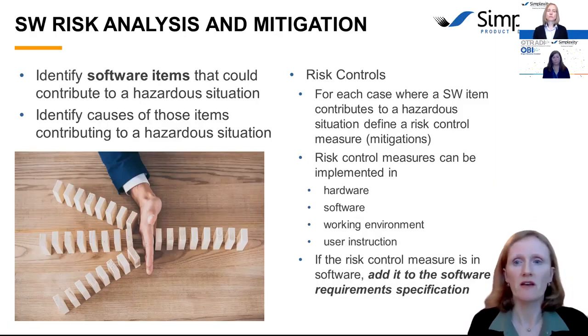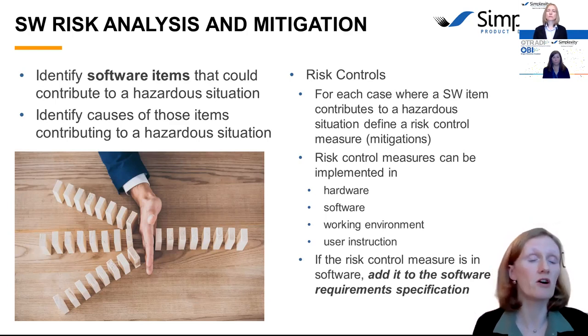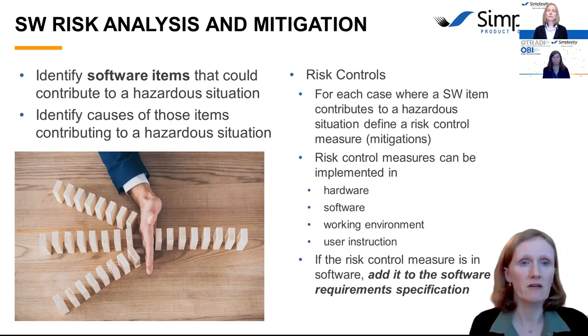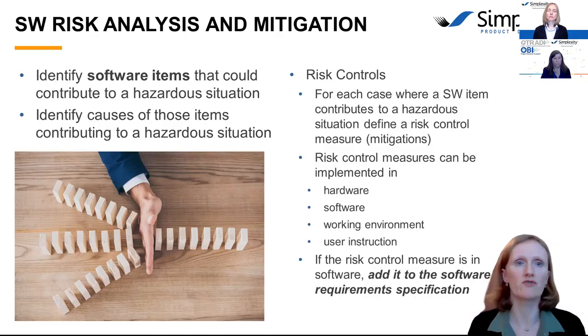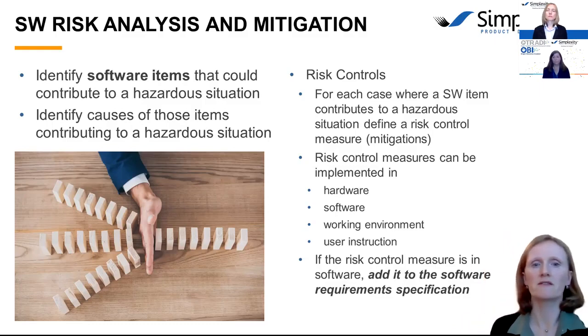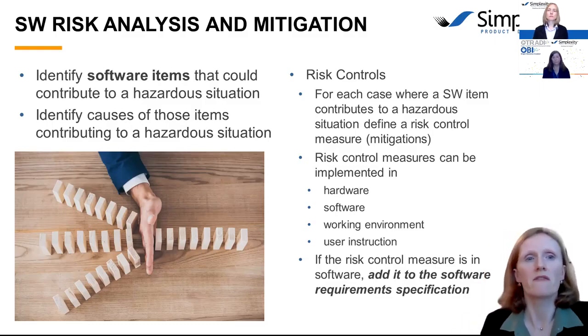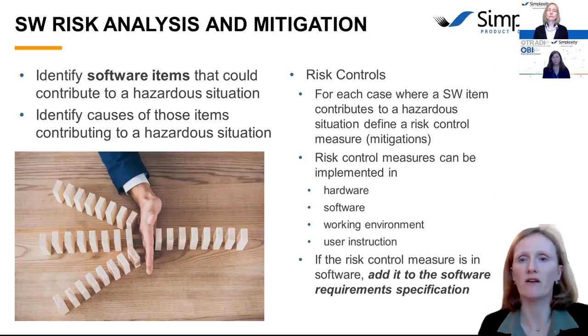Once we've identified those hazardous situations, if the risk is too high, as defined on that table, we would define a risk control measure. Those could be implemented in hardware, software, the working environment, or user instructions. And that's a priority order of where it is best to implement the risk control measure. It's obviously much safer to have a user prevented by the hardware from doing something that could lead to harm, as opposed to an instruction that warns them not to. One thing that's critical is that if a risk control measure is in the software, you add it to the software requirements specification. There has to be a requirement so that you don't lose track of these risk control measures.